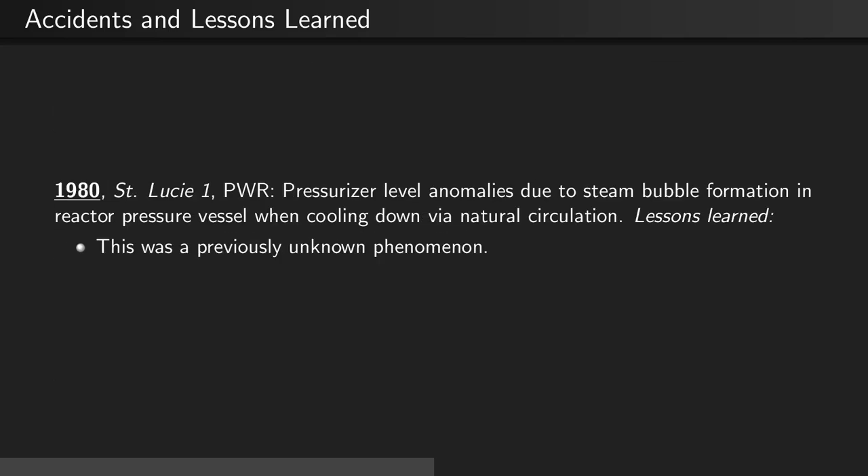Also in 1980, at St. Lucie 1, again a PWR, there was a pressurizer level anomaly due to a steam bubble which formed in the reactor pressure vessel when cooling down via natural circulation.